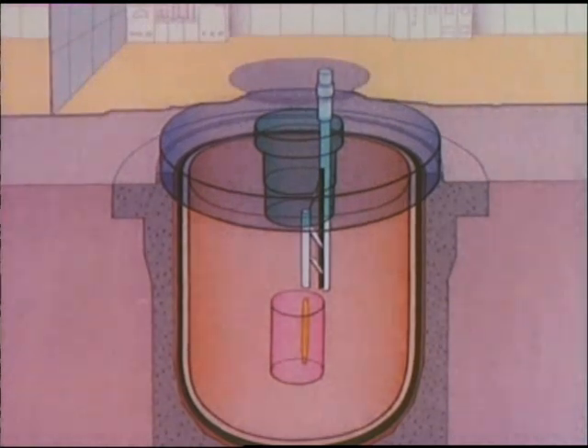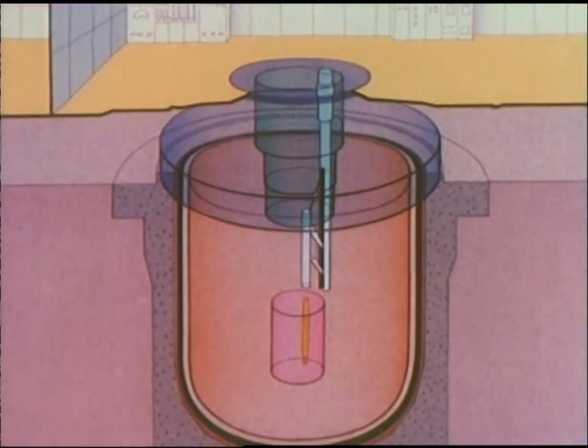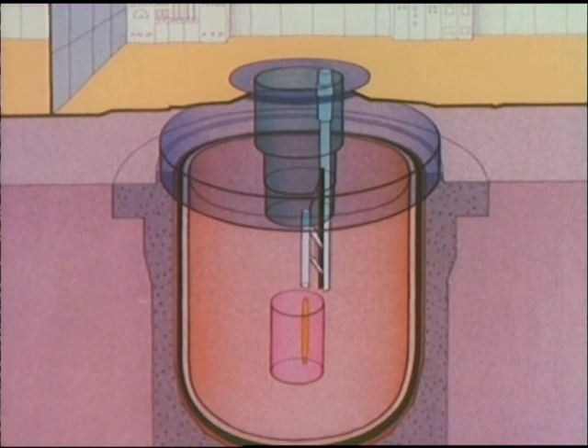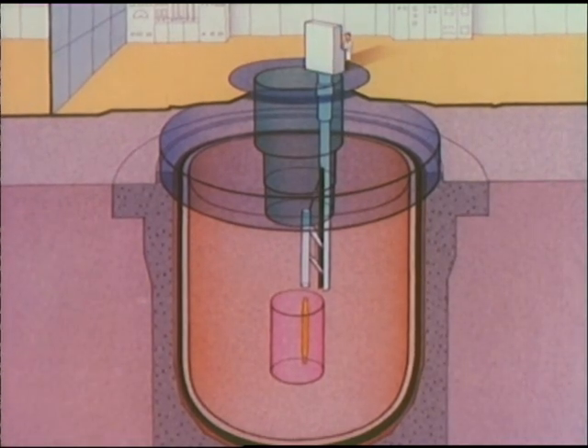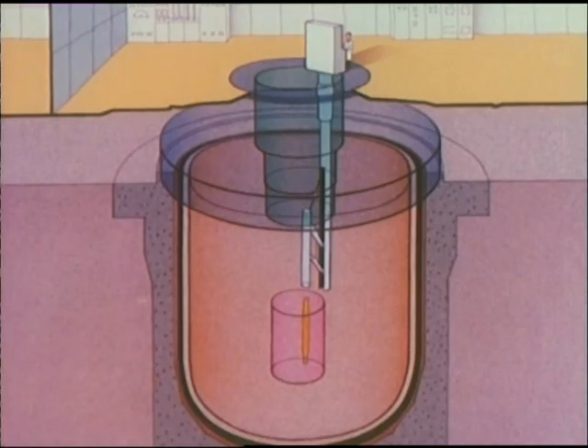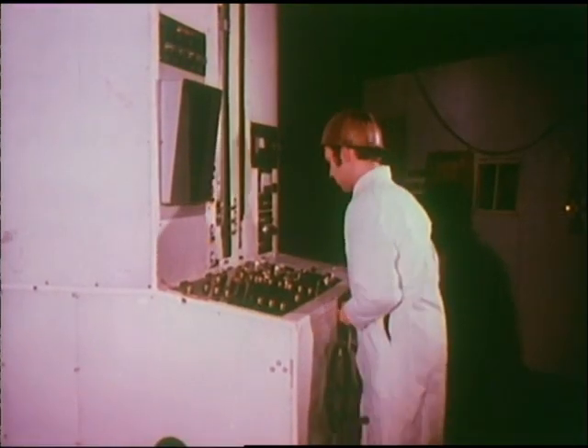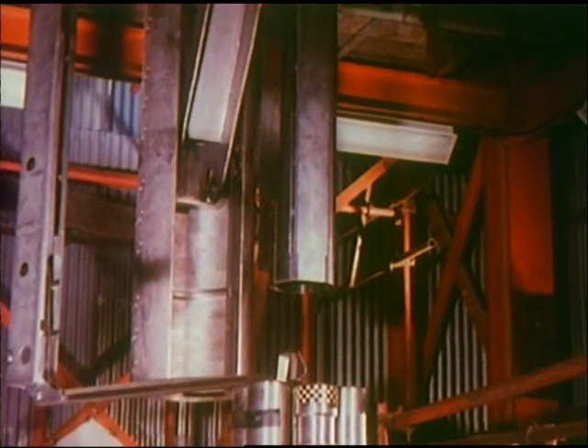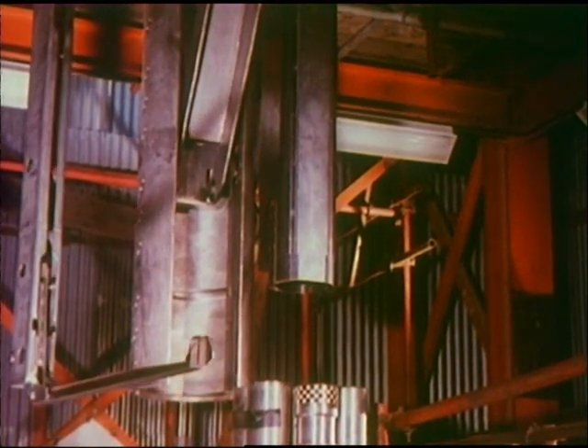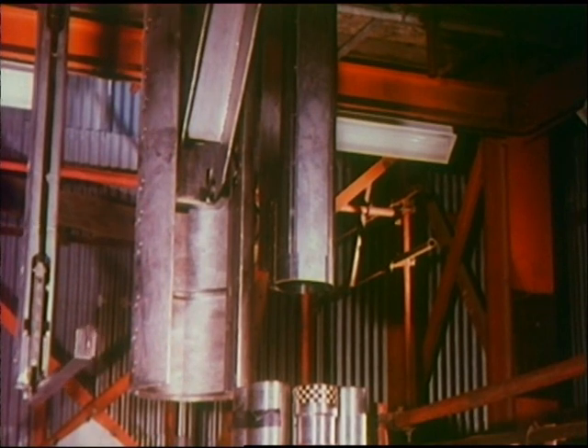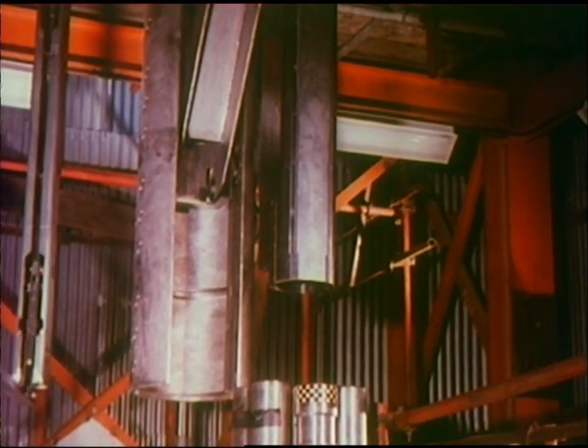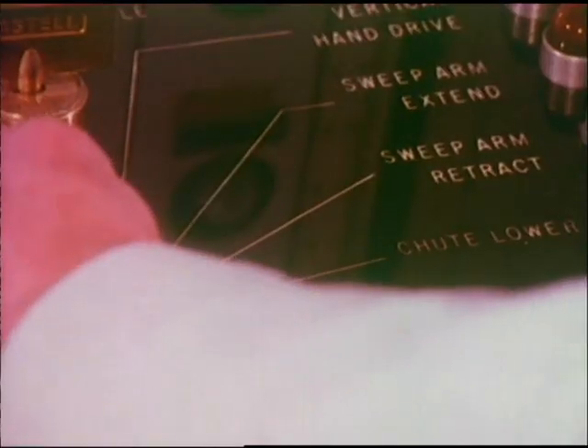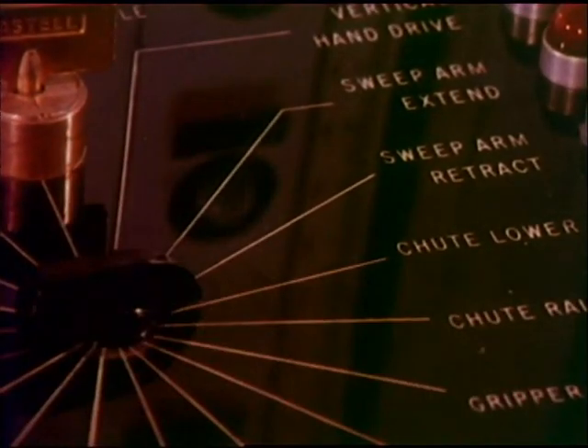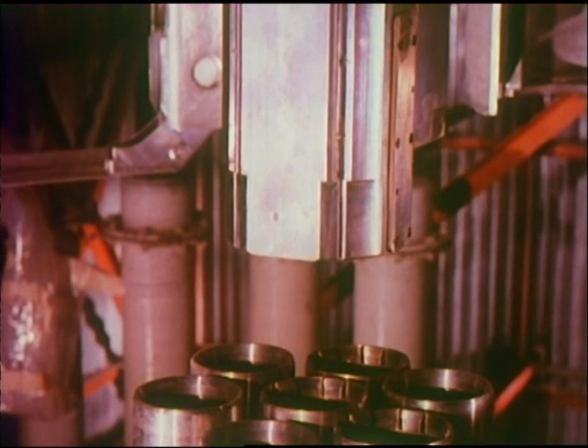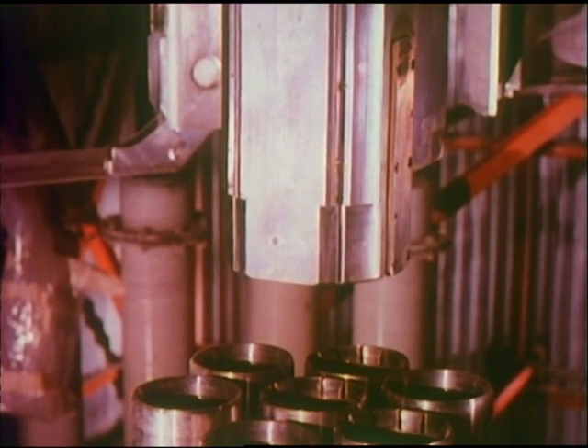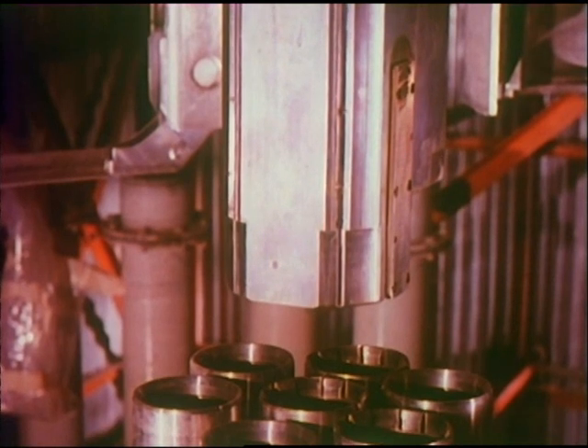Above the reactor roof, there is a clear working platform with a circular turntable in the center attached to the rotating shield below. A console is mounted in the turntable, providing the controls for the whole operation. This console was tested on a temporary rig at Dounreay. Here it is being used to operate the sweep arm, which searches the top of the core for obstructions before refueling. The test rig, which was also used for training operators, enabled the refueling system to be studied outside the reactor. Under operational conditions, the refueling machine will of course be submerged in liquid sodium.